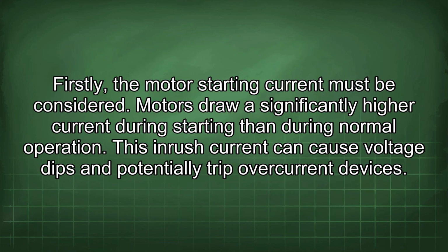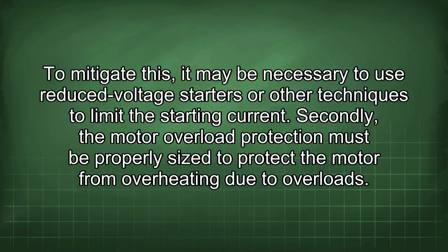Firstly, the motor starting current must be considered. Motors draw a significantly higher current during starting than during normal operation. This inrush current can cause voltage dips and potentially trip overcurrent devices. To mitigate this, it may be necessary to use reduced voltage starters or other techniques to limit the starting current.